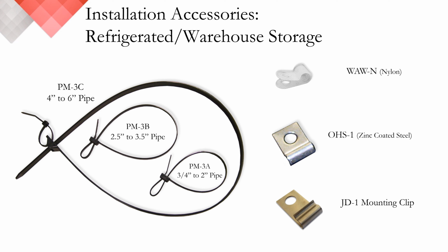At the ceiling level, the opportunity for damage is greatly reduced. In this area, it would be advisable to follow the sprinkler pipes and attach directly if at all possible and permitted. To do so, we recommend double loop pipe straps. This provides your installers the ability to cinch the cable tie to the pipe securely without compromising the detector. The first loop serves as your anchor, whereas the second loop provides a taut but loose support of the detector to avoid any damage. For in-rack, we have a variety of clips available to accommodate the installation, including our WAW, OHS clips, and our newly introduced JD1 clip.